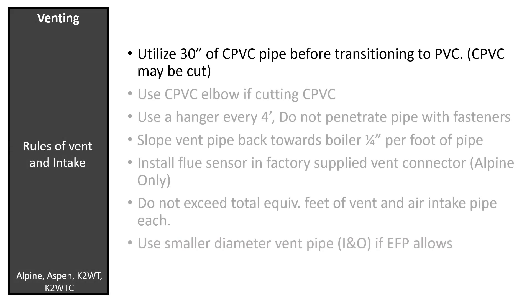The vent kit may be an option and consists of a 30-inch piece of cPVC pipe, a cPVC close radius elbow, PVC coupling for vent termination, a 90-degree elbow for air intake termination, and two rodent screens. Starting at the boiler, use all 30 inches of cPVC pipe. When needed, you can cut the cPVC pipe and install the cPVC elbow. If the pipe was cut, use the remaining cPVC before transitioning to PVC. Be careful to remove all cutting debris and clean the cut end of the pipe — this will keep the shavings out of the burner assembly.